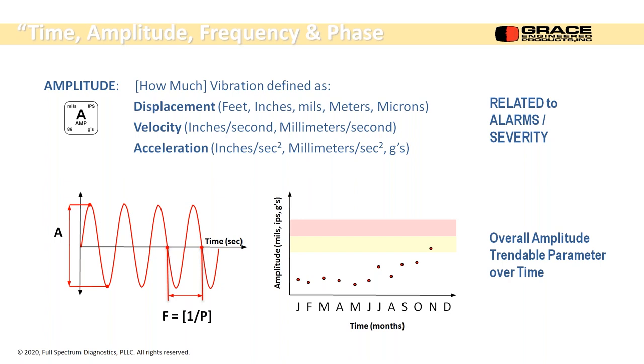They get fantastic trends. This would be like January, February, March, April, all that for route-based measurements. You get 12 measurements a year. If I took a measurement every day, I'd get 365 measurements with the in-place wireless transducers. If I took it every hour, I'd have almost 8,800 measurements. Every minute, 350,000, something like that, something ridiculous. There is data overload, but you're going to get fantastic trends in this. You'll be able to see real subtle changes that are from plant processes instead of just motion from month to month, taking the transducer on and off, things like that. Okay, great trends. So amplitude-wise, that's what we're doing.